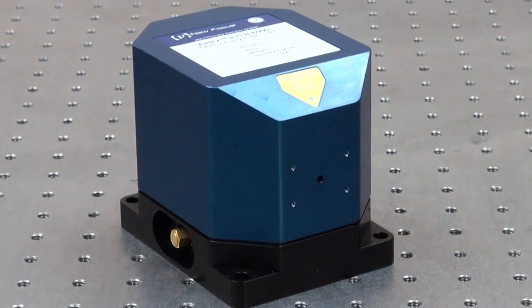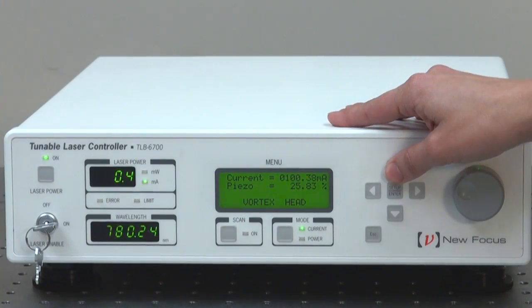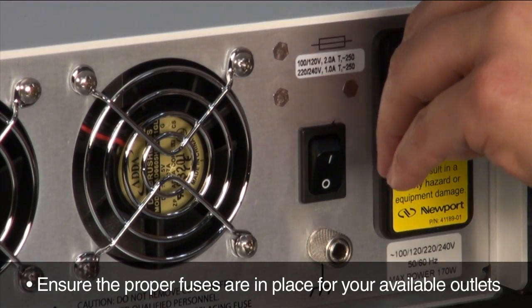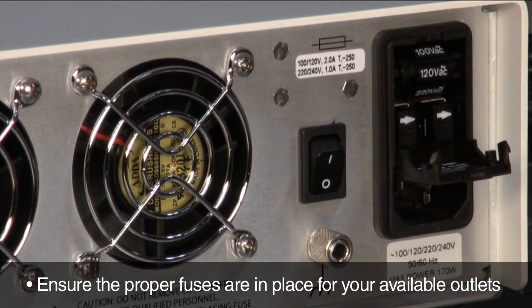Setup and operation of all New Focus lasers are extremely simple. The first step in turning on your Vortex Plus is to ensure that you have the proper fuses in place in the TLB-6700 controller according to your electrical outlet requirements.